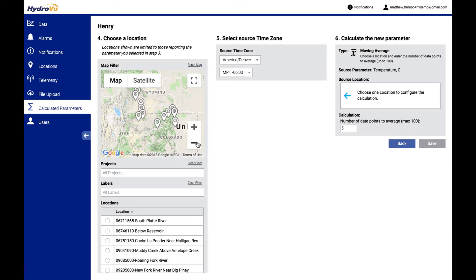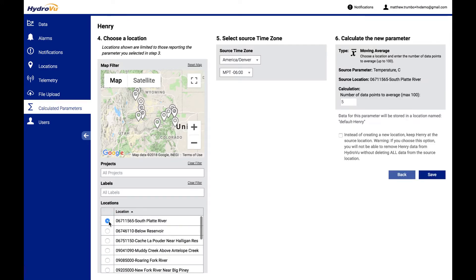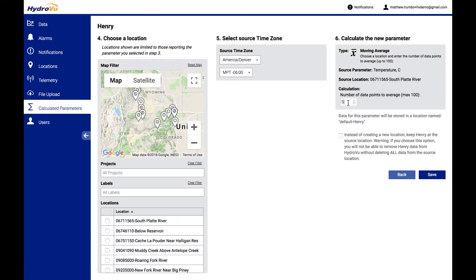what you could do is actually calculate a moving average across this here. So we default to five data points to average. It's the last five, but you can go up to 100 or as few as two to just smooth out that data if it's particularly spiky. This is really useful for our customers that use turbidity.